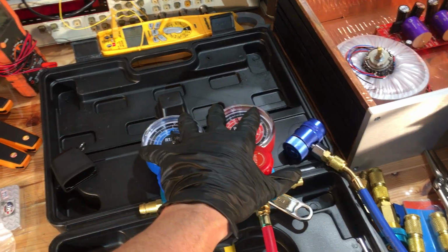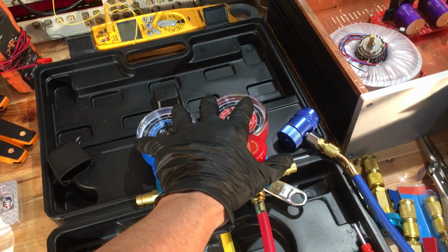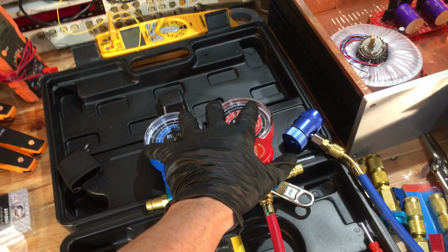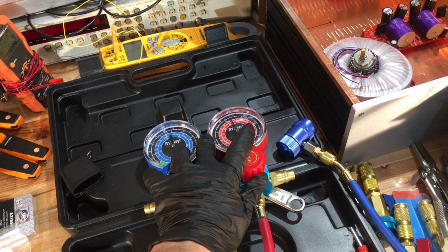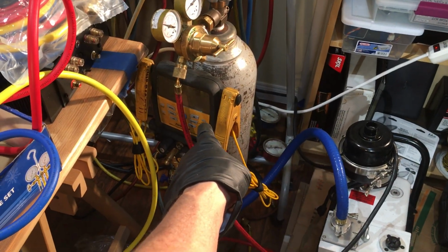So this gauge set would fail. I would not use this to do an hour or several hour long pressure drop test. That's where these gauges from Fieldpiece work really good, or Testo.